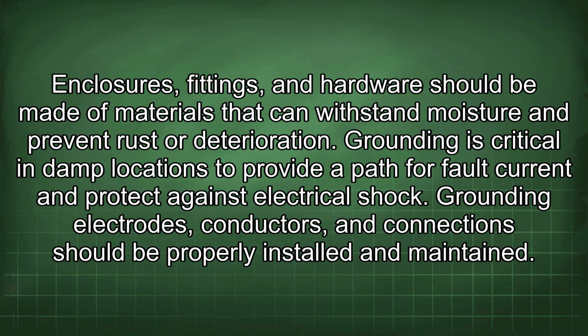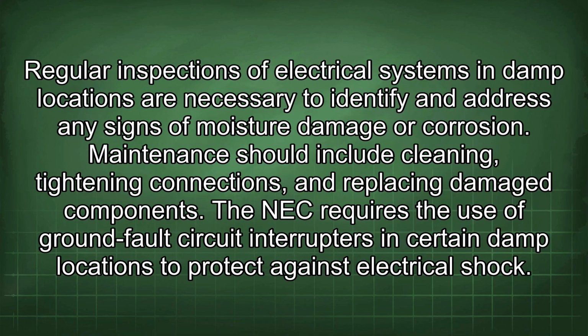Grounding is critical in damp locations to provide a path for fault current and protect against electrical shock. Grounding electrodes, conductors, and connections should be properly installed and maintained. Regular inspections of electrical systems in damp locations are necessary to identify and address any signs of moisture damage or corrosion. Maintenance should include cleaning, tightening connections, and replacing damaged components.